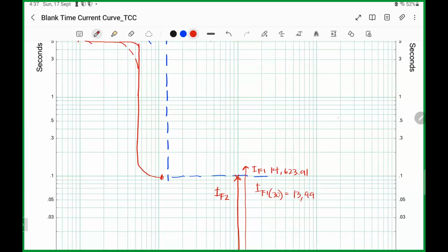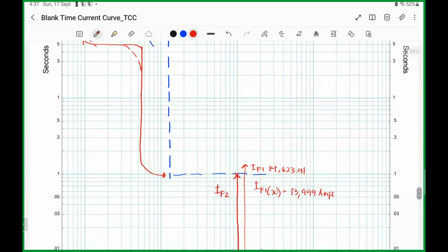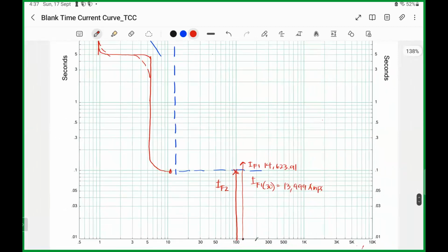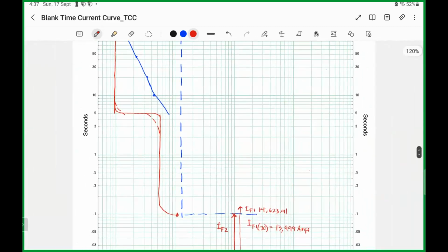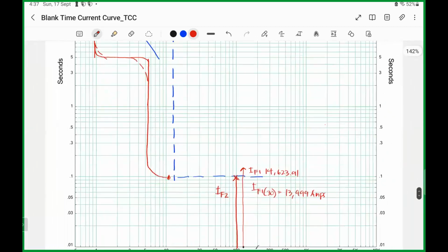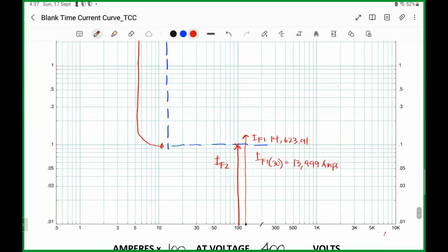13,999. So you can check this one so that you also have practice, but the concept of finding the fault current with respect to the TCC as well. You saw how it was done, so you can double check it. So the I fault is 13,999, which is the minimum fault. It's just slightly ahead of it here. It's a close value, so I assume it falls here.